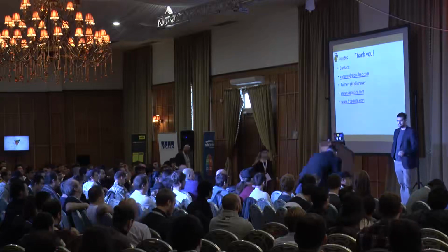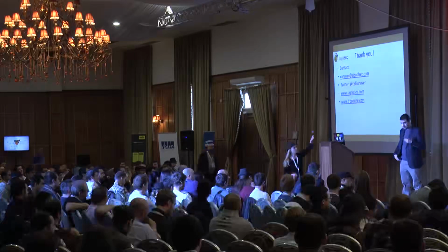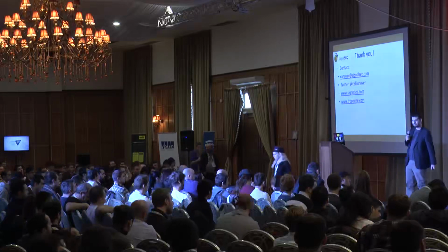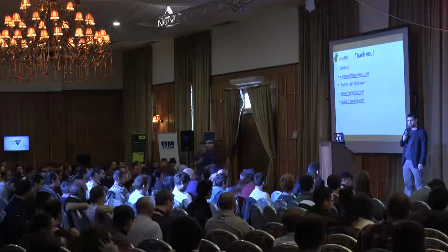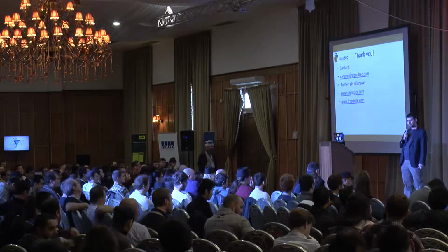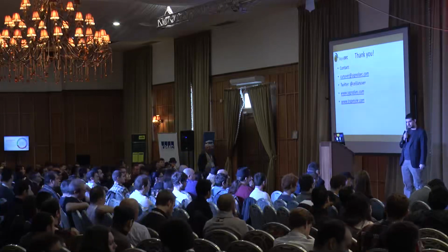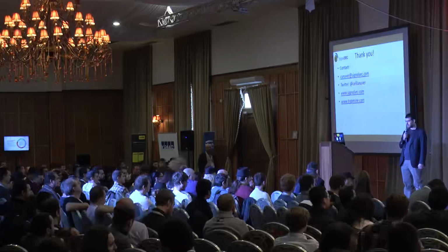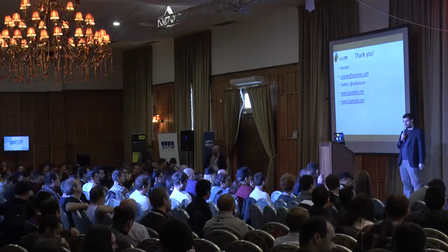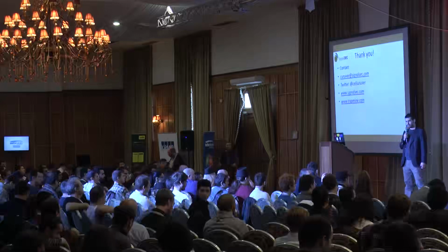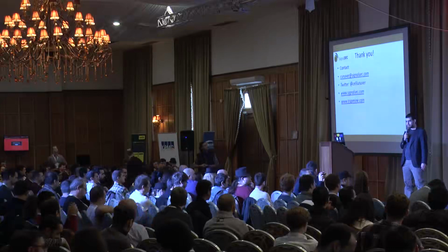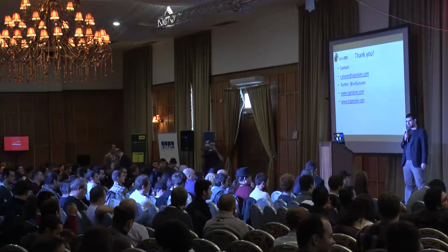There was a talk by the guys at Digital Bond at S4 Japan a couple of months ago or so about CodeSys version 3, because there were some vulnerabilities related to unauthenticated communications in CodeSys version 2. CodeSys is a runtime framework that is used by many other vendors. Yes, exactly. And it turns out that they've issued a patch for CodeSys version 2, but then the same issue happened in CodeSys version 3, showing that this vendor basically patched the issue in one of its products, then it came out with a new product that basically had the same vulnerability.